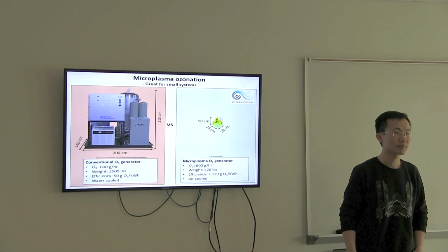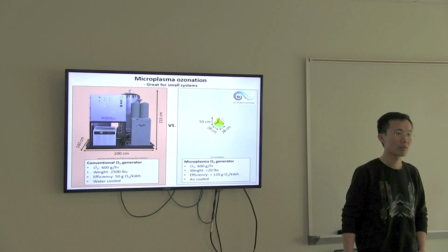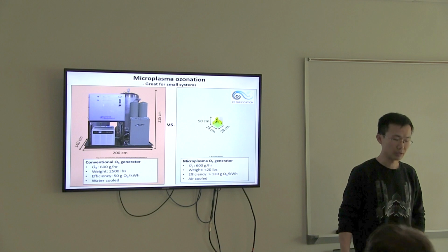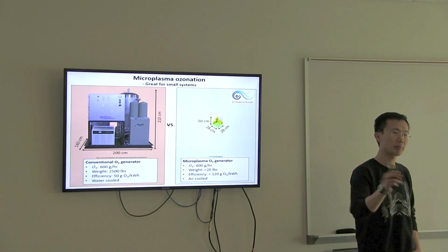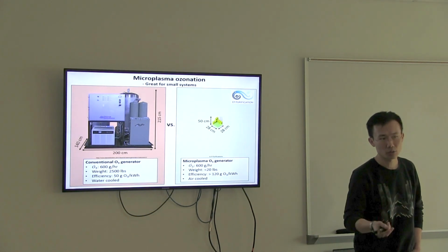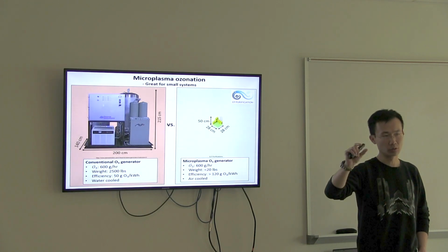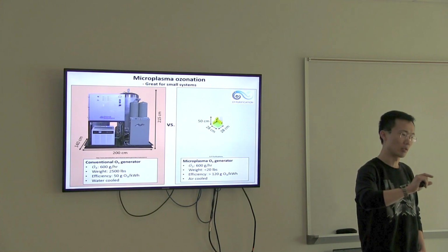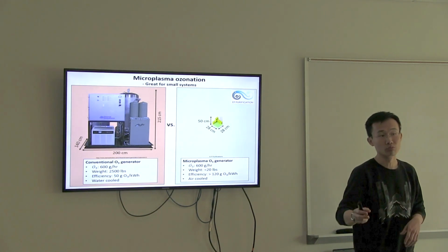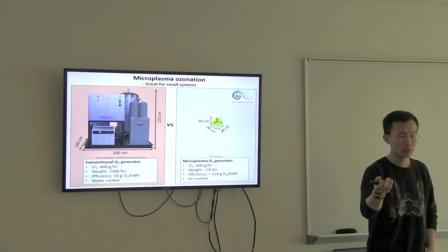I'm sorry again. What injection rates of ozone are people using for efficacy? Like how many grams per liters or whatever. So depending on your target pathogen, for more resistant pathogens you need more, and also depending on the water quality, as Zach was saying, the higher organic loading you have, part of this ozone is consumed when you have organics in your system. That part of the ozone is not going to react with your pathogens. So with higher organic loading, you would probably need higher ozone.